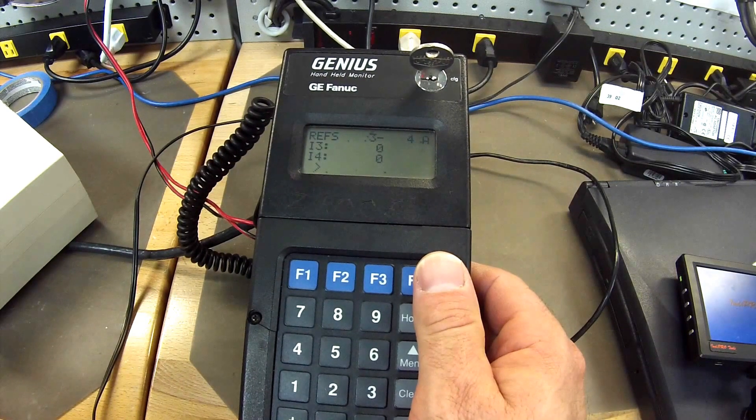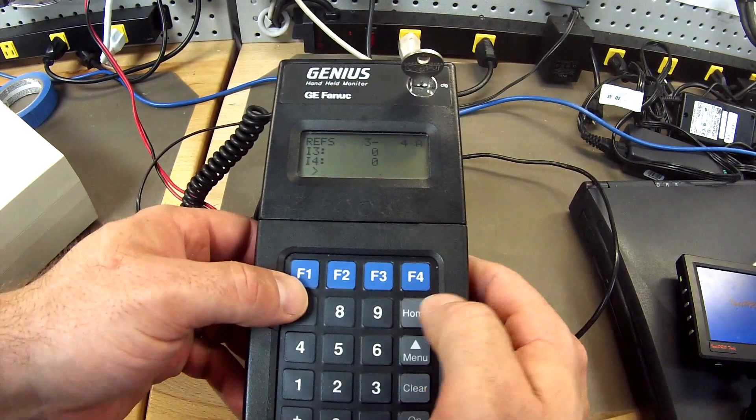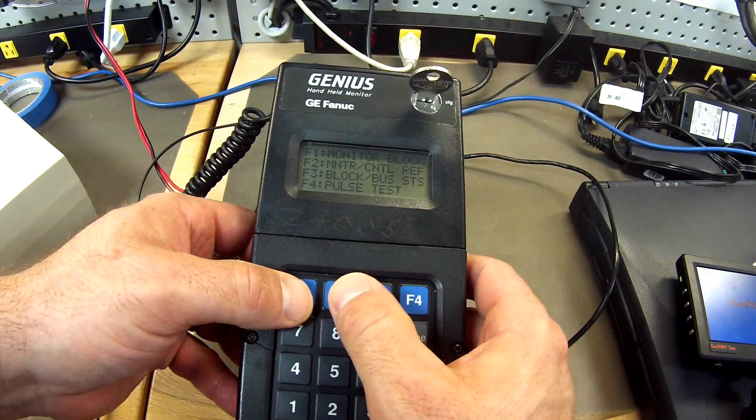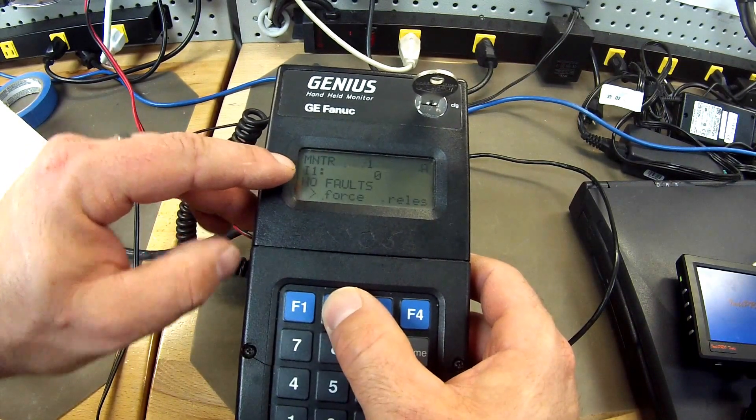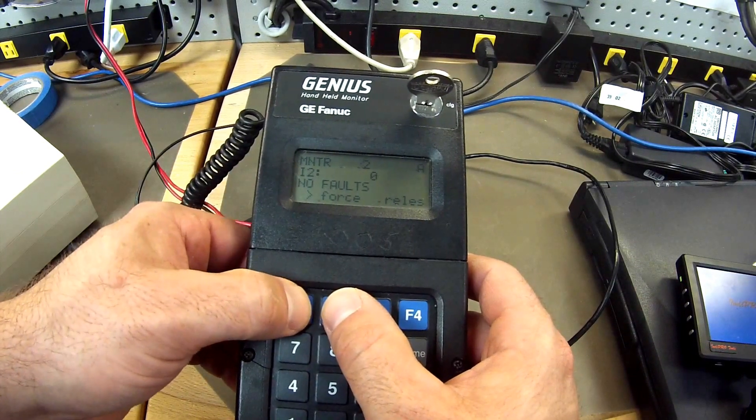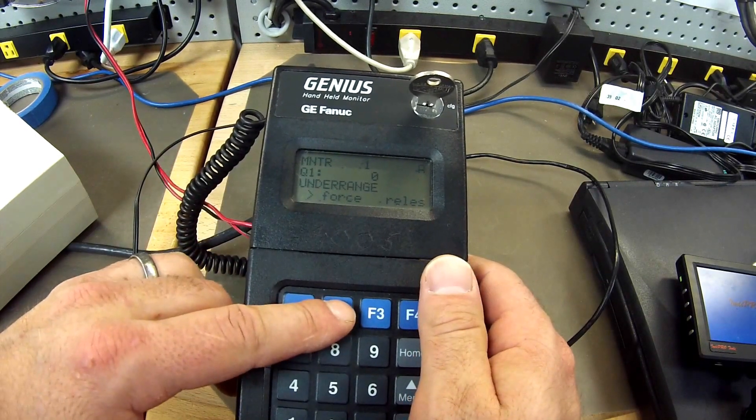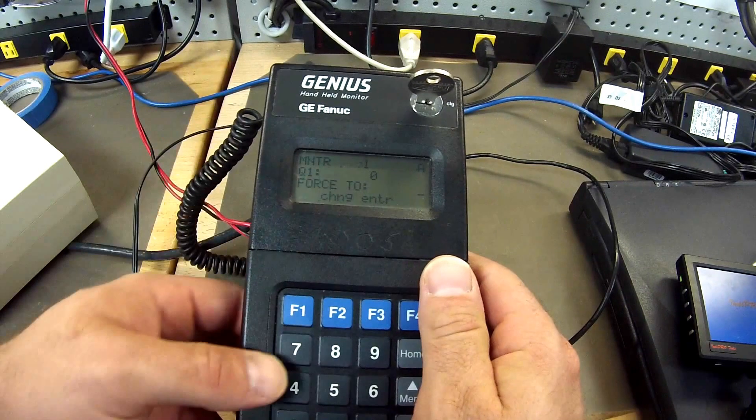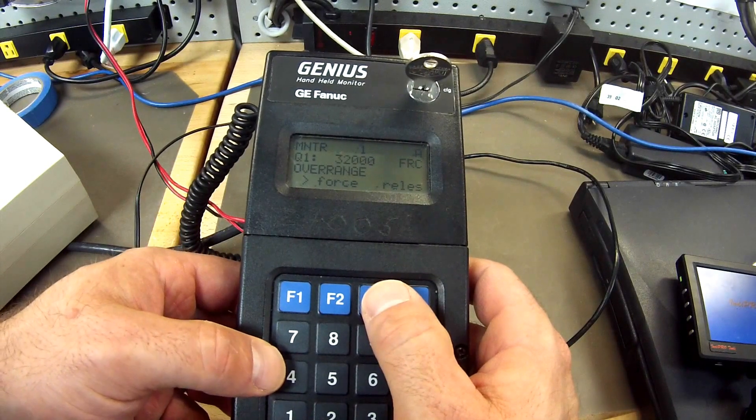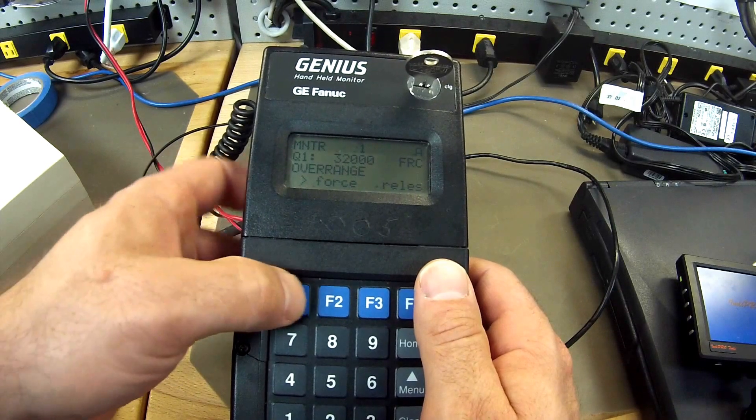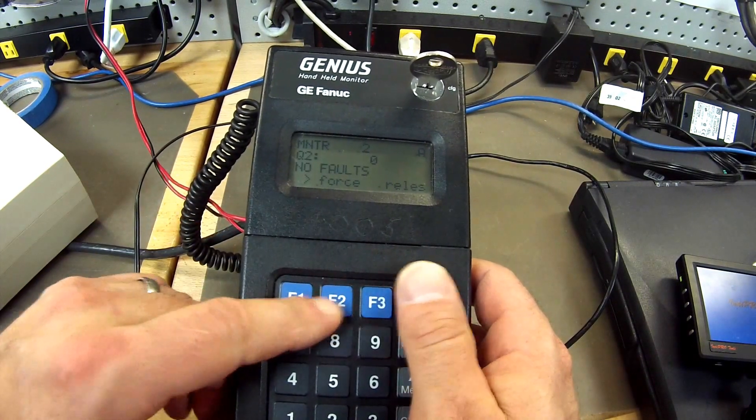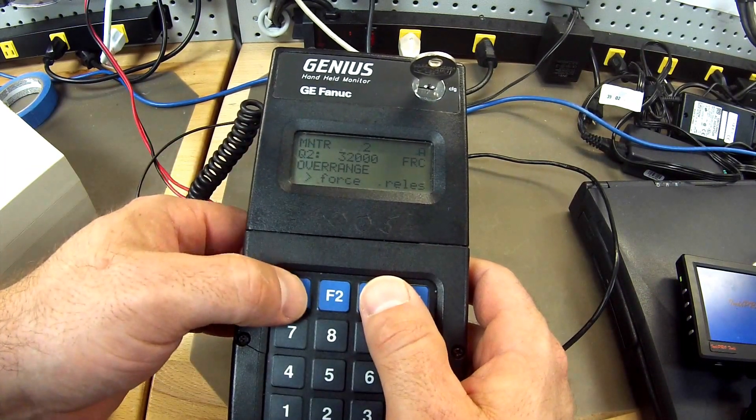Next thing you want to check, since we are on voltage. Again, I am on the monitor. Is the output. So I am going to go back one. I am going to click menu. And F2 monitor. Now we are going to go, this is input 1, input 2, 3, 4, output 1. Now I can force a value in there. As you remember my high range was 32,000. So what I am going to do is force F2, 32,000. For a round figure. I am going to click enter. Now that is forced into the system. Now I am going to go to output 2. Same thing. F2, force, 32,000. F3, enter. Now that value is in there. I am going to go back to 1. Here is what I am going to do.